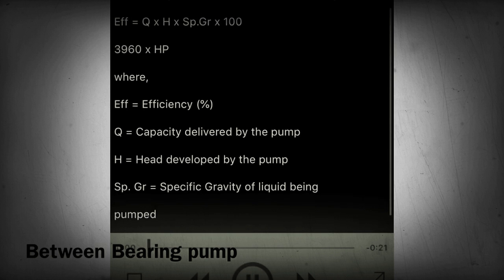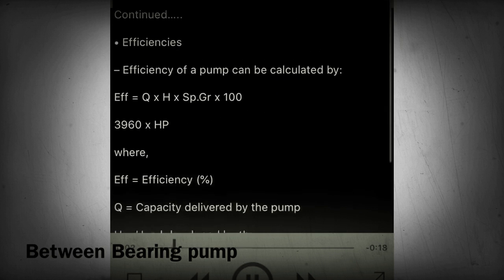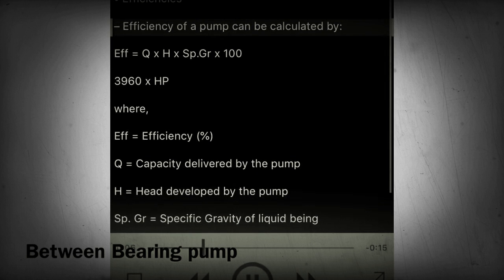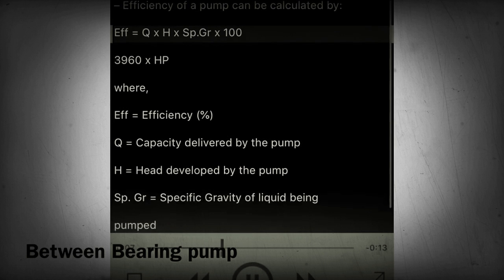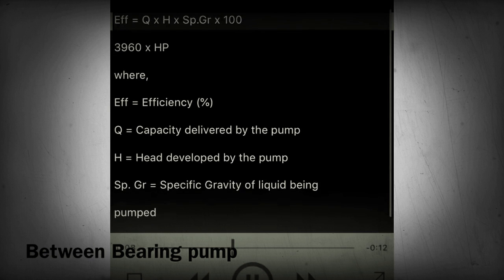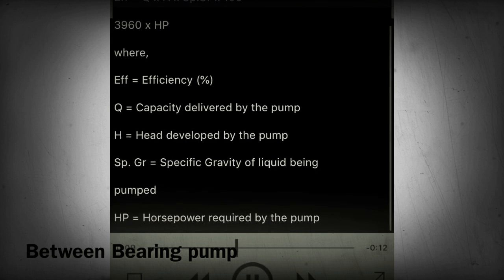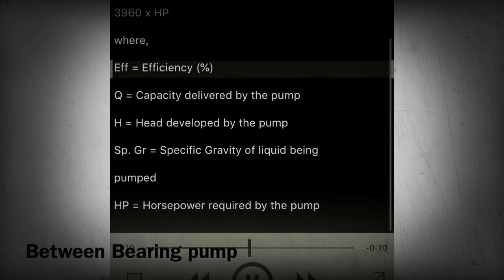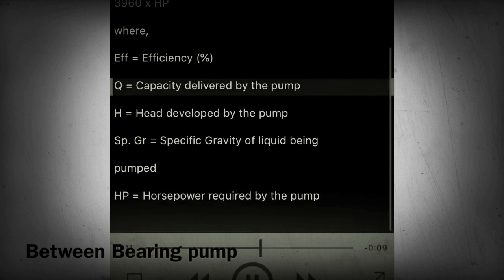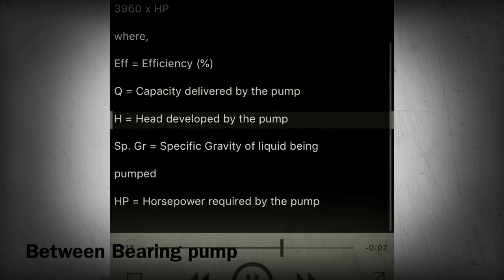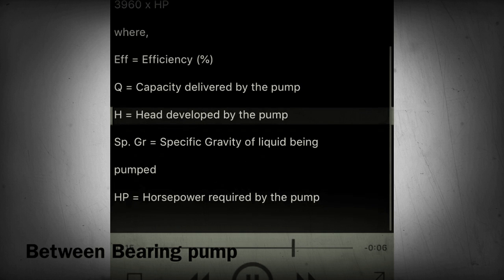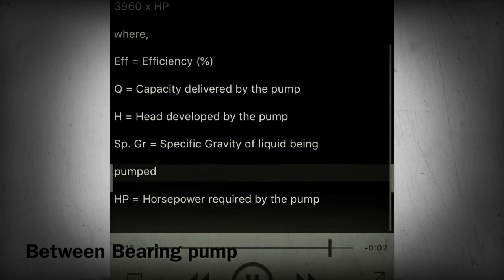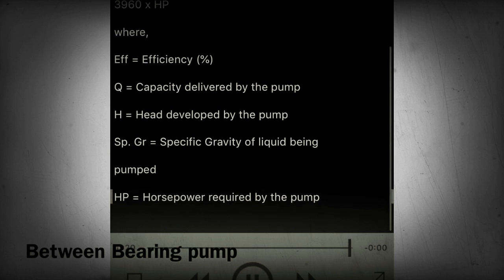Section 24 - Centrifugal pump curves: efficiencies. Efficiency of a pump can be calculated by: E = (Q × H × SPGR × 100) / (3960 × HP), where E equals efficiency (percent), Q equals capacity delivered by the pump, H equals head developed by the pump, SPGR equals specific gravity of liquid being pumped, and HP equals horsepower required by the pump.